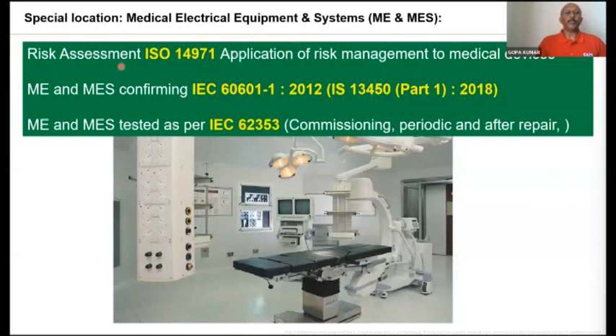First, you should make a risk assessment, because, for example, the operation theater is an oxygen enriched area. The amount of oxygen is very high. The chance of even a small spark becoming a major fire is much more. Also, a lot of chemicals or chemical contents are there in that particular area. A lot of different kinds of risks are there in that area. The first point is you should make a risk assessment as per ISO 14971. And you have to find out what kind of safety measures you may need to implement in case of any problem. It can be an electrical problem or a chemical problem, or some other things.